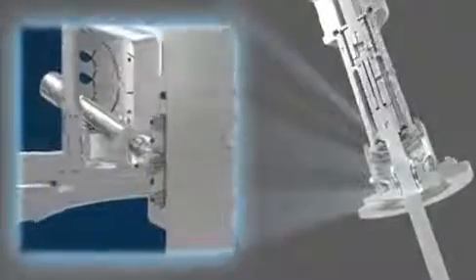Double mechanical sealing keeps a sterile barrier between the tank and the atmosphere. The seal is constantly flushed with condensed steam at high temperature, typically used in high-pressure applications such as aseptic storage tanks and fermentation tanks.